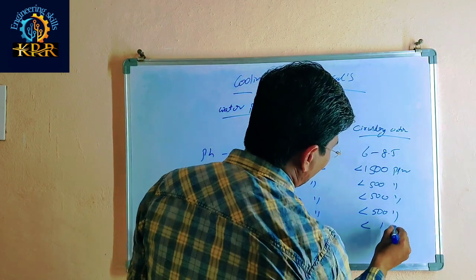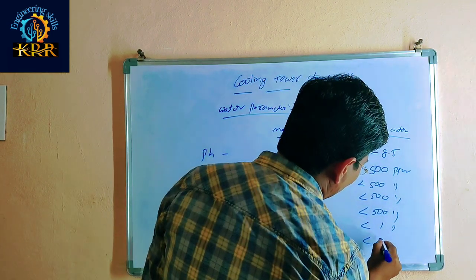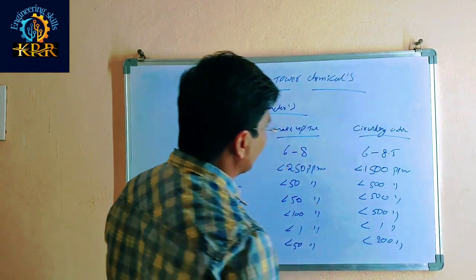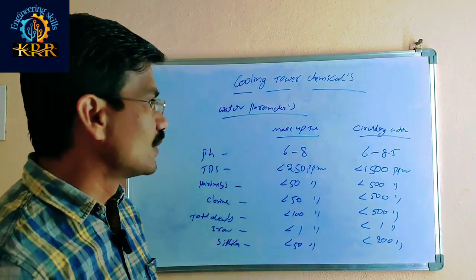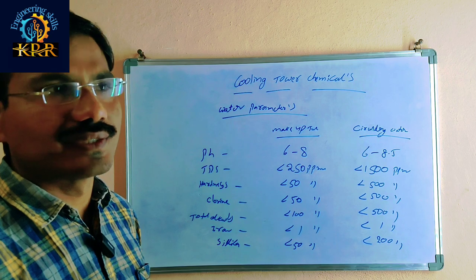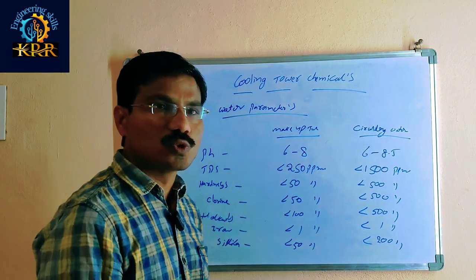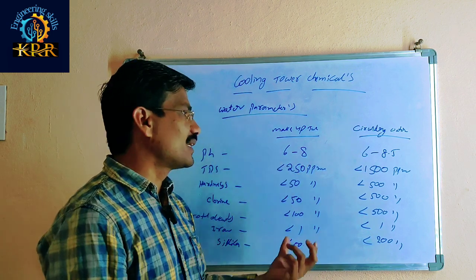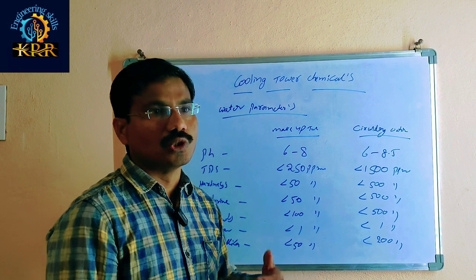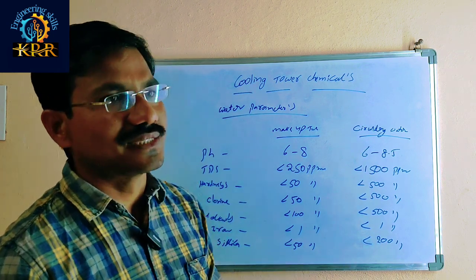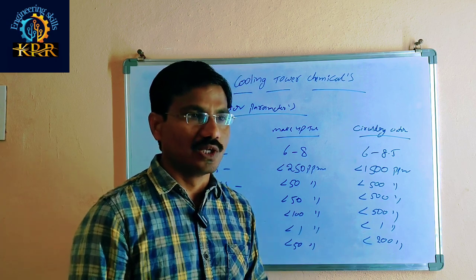For silica: less than 50 ppm in makeup and less than 200 ppm in circulation. These water parameters should be maintained to standard values. If these parameters are not maintained, you will face problems in the condenser and evaporator.